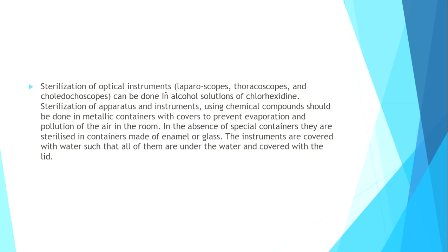Sterilization of optical instruments, laparoscopes, thoracoscopes and other endoscopes can be done in alcohol solutions of chlorhexidine. Sterilization of apparatus and instruments using chemical compounds should be done in metallic containers with covers to prevent evaporation and pollution of the air in the room. In the absence of special containers, they are sterilized in containers made of enamel or glass. The instruments are covered with water such that all of them are under the water and covered with the lid.